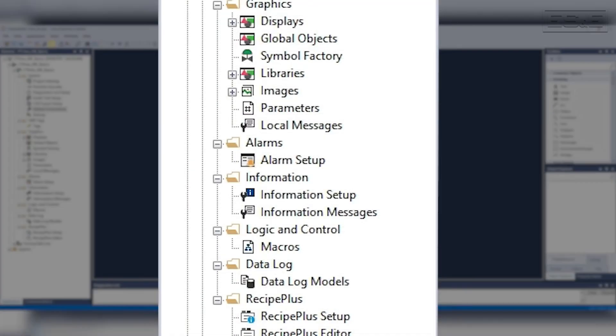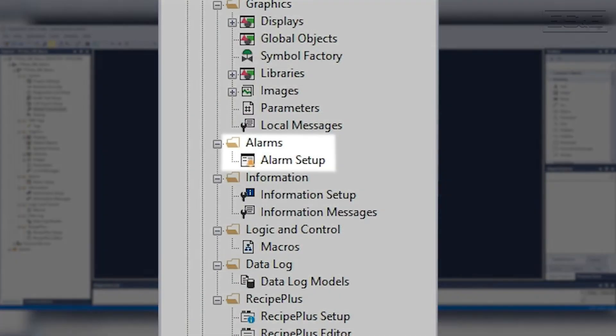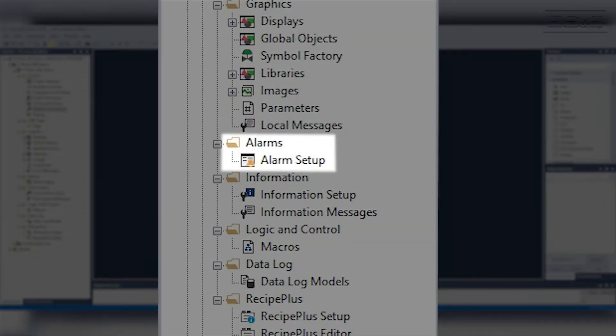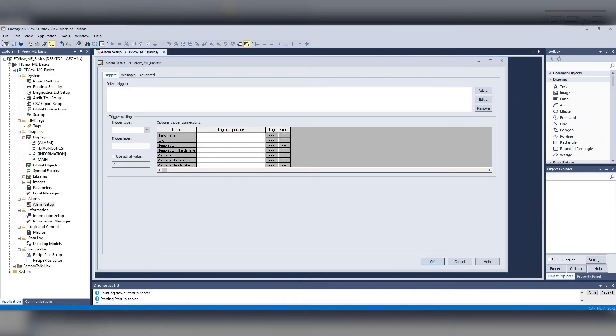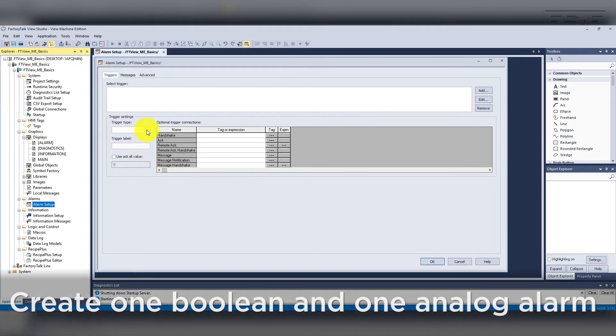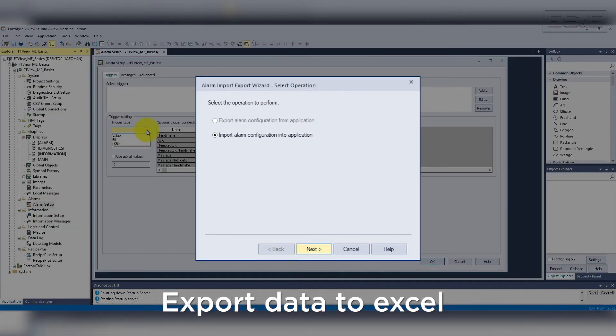The last area we will highlight is the Alarms Setup Folder. The newer PanelView 5000 uses tag-based alarming, but in Machine Edition you need to create the alarms individually. What I would recommend is to create one boolean and one analog alarm, then export the Alarm Setup database to be edited inside Excel.